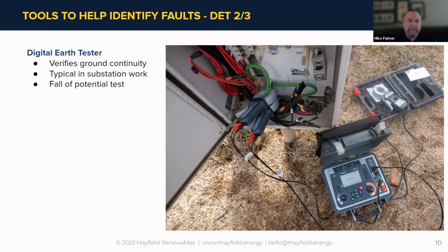So when Ryan mentioned the substation, you've got a grid. Even in a solar PV array, you have a substation. In most cases, some are direct connected, but you still have a ground grid in that sub on the PV array. So you still need the type of tester that has the filtering ability, like the DET 2/3, to do the testing that's needed inside the fence.